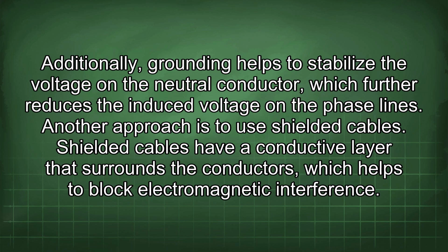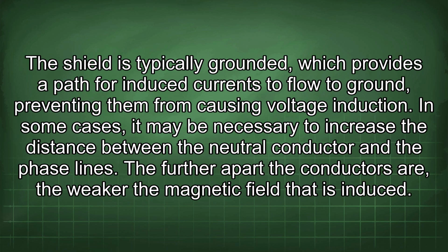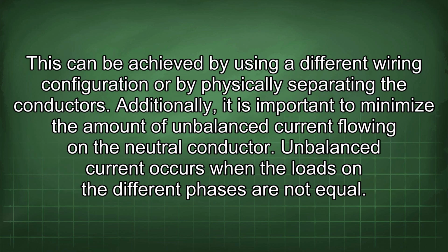Shielded cables have a conductive layer that surrounds the conductors, which helps to block electromagnetic interference. The shield is typically grounded, which provides a path for induced currents to flow to ground, preventing them from causing voltage induction. In some cases, it may be necessary to increase the distance between the neutral conductor and the phase lines. The further apart the conductors are, the weaker the magnetic field that is induced. This can be achieved by using a different wiring configuration or by physically separating the conductors.